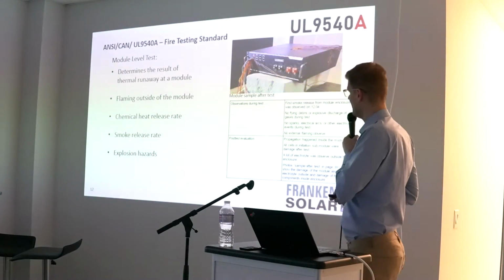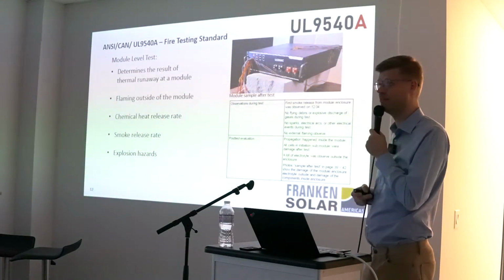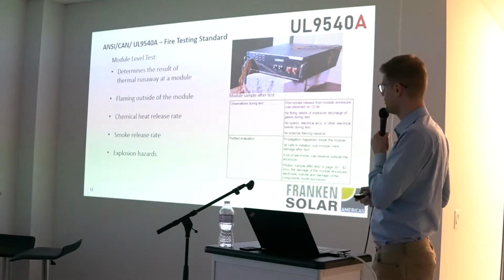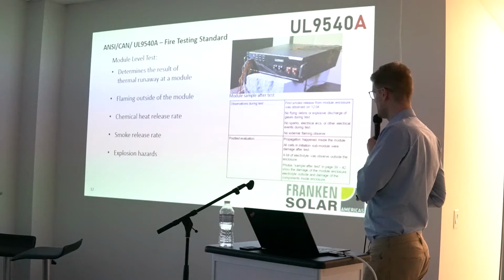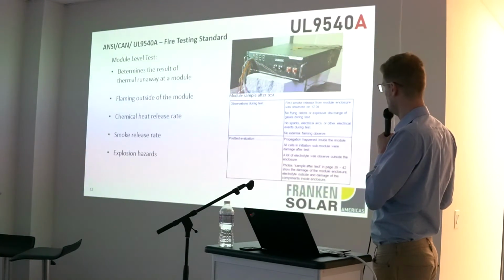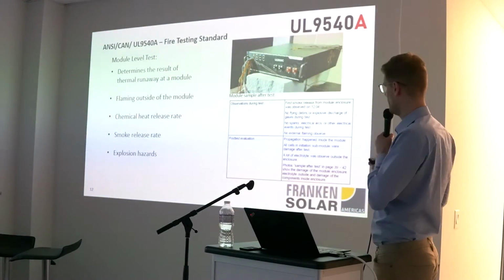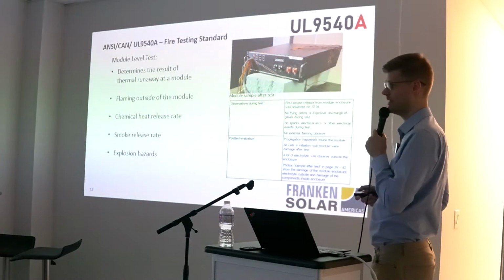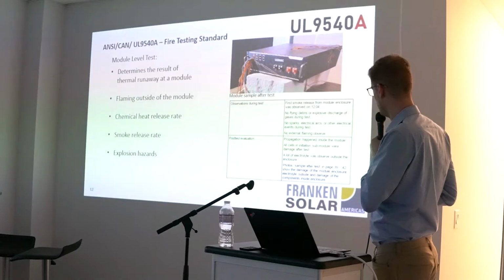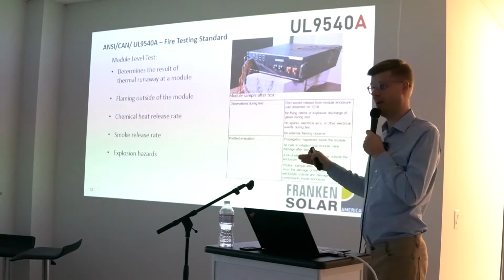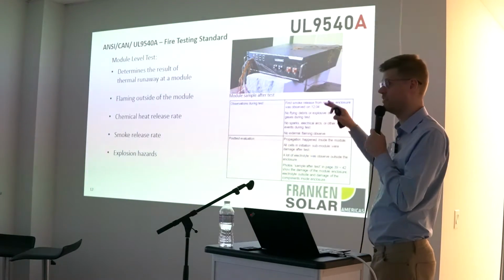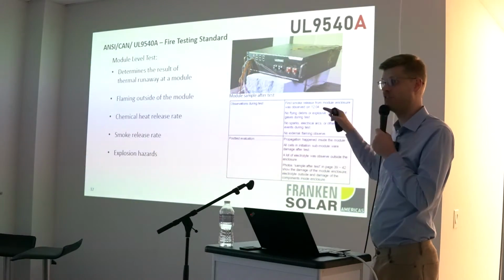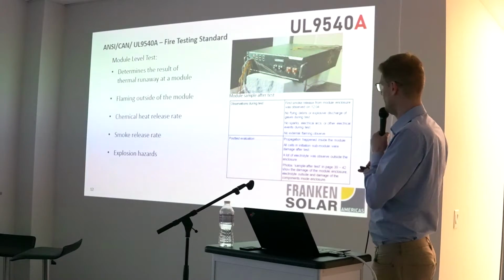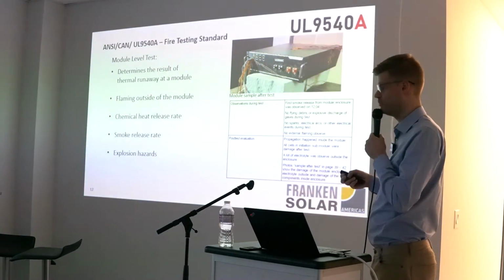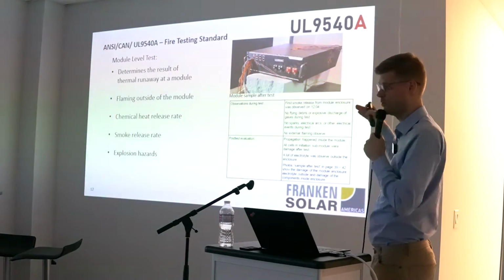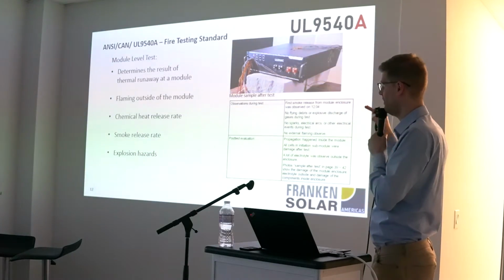Here we have a picture from a battery manufacturer we are carrying, from their UL9540A test, and I put a little screenshot from the test report. And you see here, observations during test: first smoke released from module at a certain time, no flying debris or explosive discharge, so that's very good. No sparks, no arcs or other electrical events during test, perfect. No external flaming observed. So the cell itself did not pass, but the whole system was put into a cabinet, and the cell within the cabinet was actually able to pass that testing. So you see the brand, multiple other brands of battery modules and cells also are compliant with that module level test and pass the test at this point.